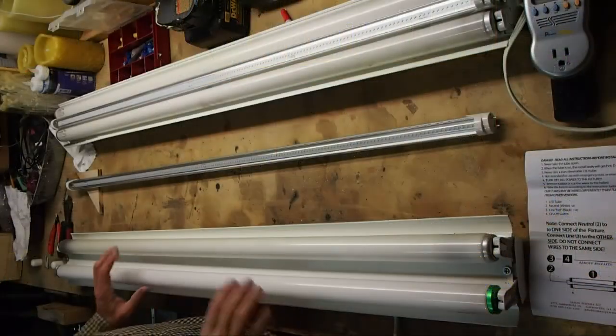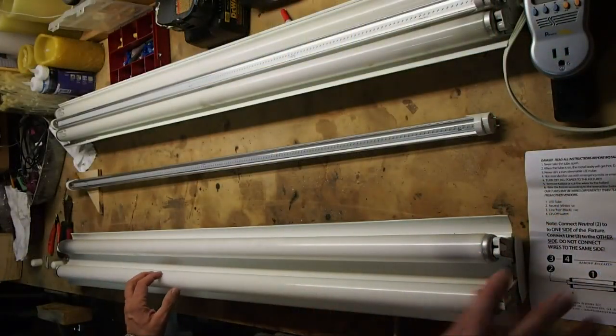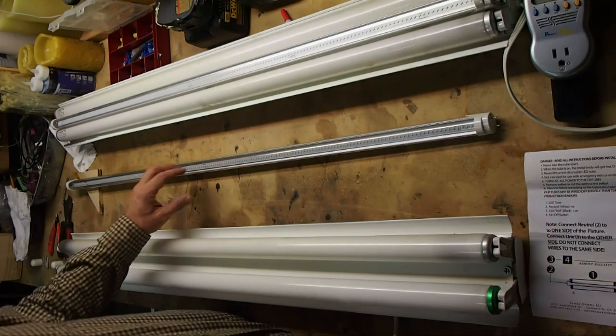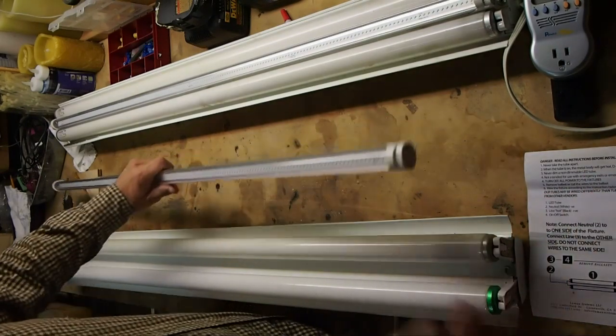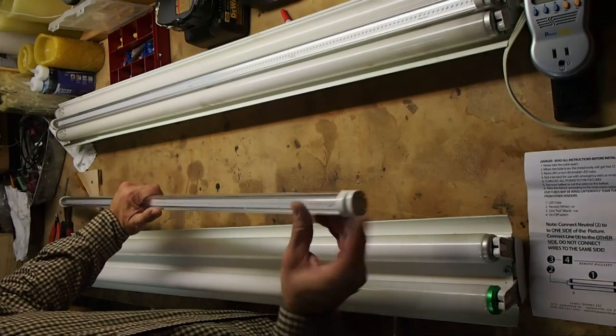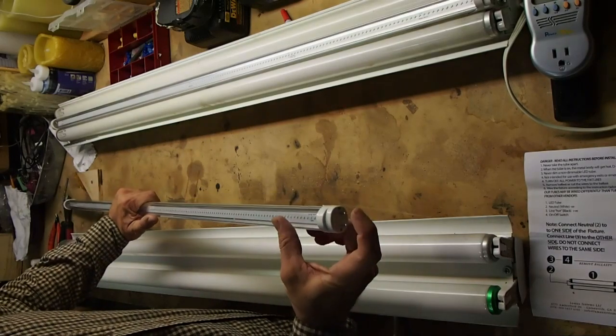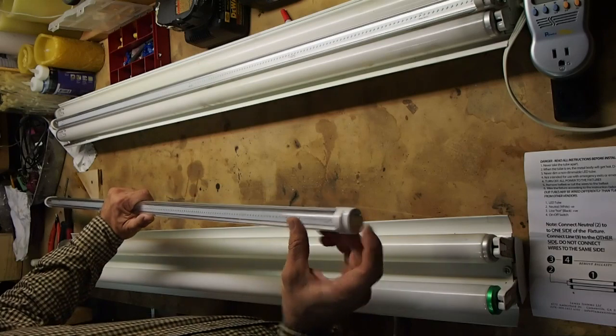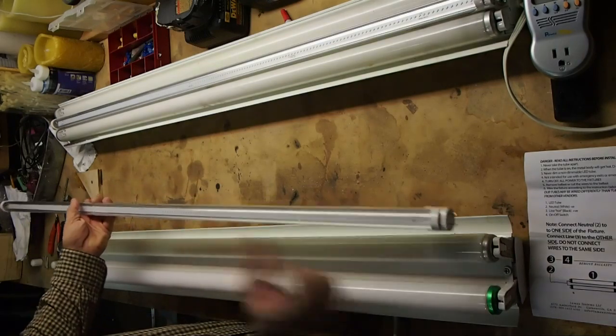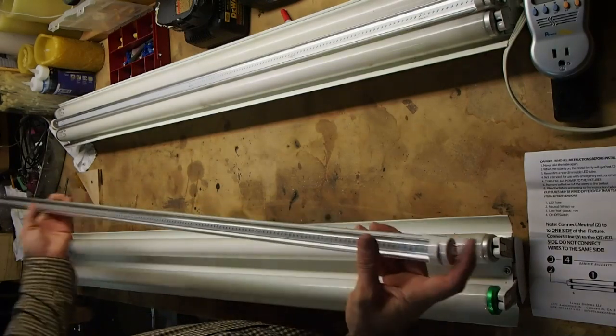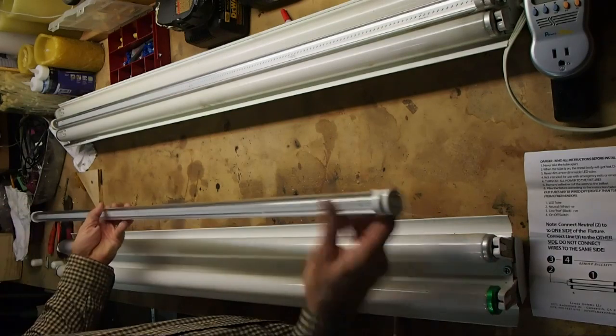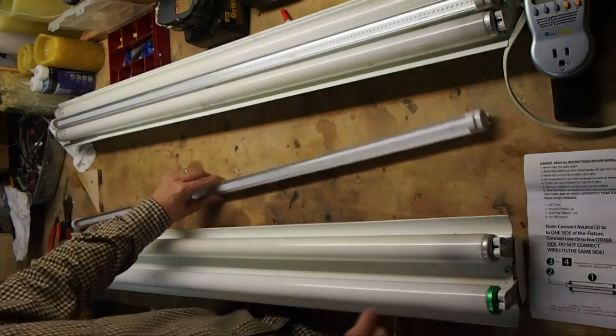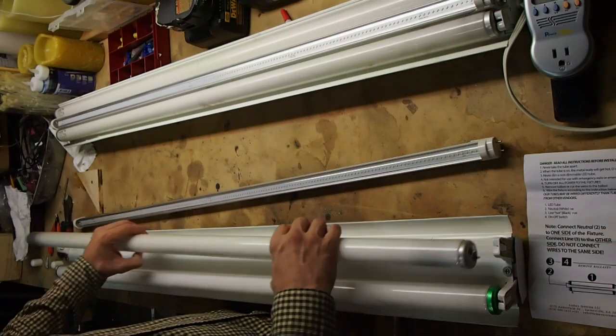Okay, so let's take a look at how to change these out. Now, the most important thing to do is to check your instructions and to show how these are wired. This is especially important because some tubes require neutral and power on one side, but this particular tube requires neutral on one end and power on the other. So check your instructions so you know how. It's fairly simple in this case. So let's just take this apart.